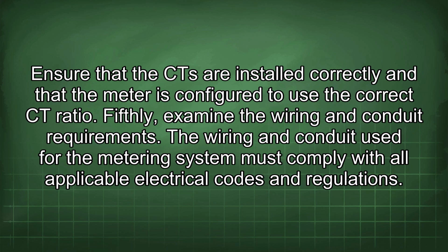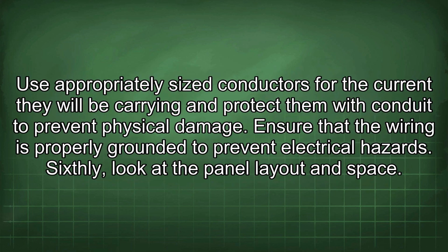Fifthly, examine the wiring and conduit requirements. The wiring and conduit used for the metering system must comply with all applicable electrical codes and regulations. Use appropriately sized conductors for the current they will be carrying and protect them with conduit to prevent physical damage. Ensure that the wiring is properly grounded to prevent electrical hazards.